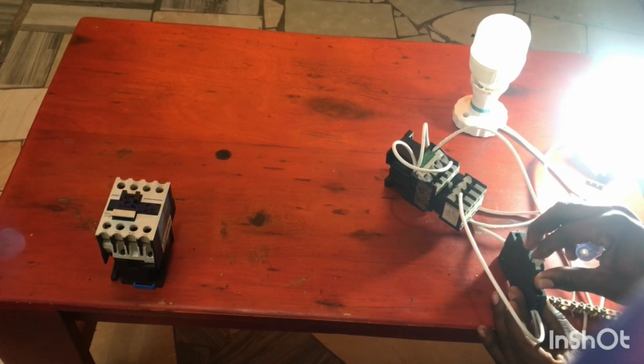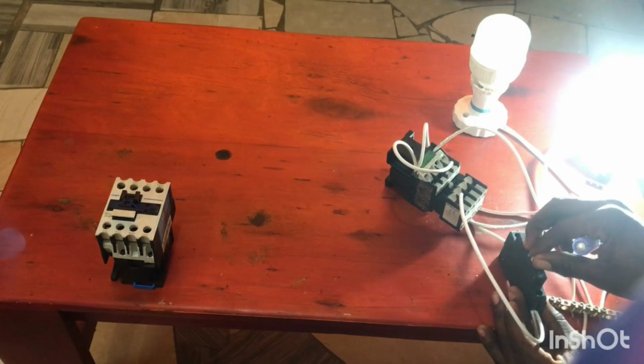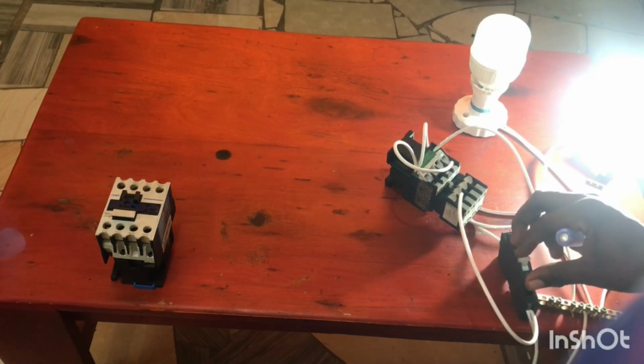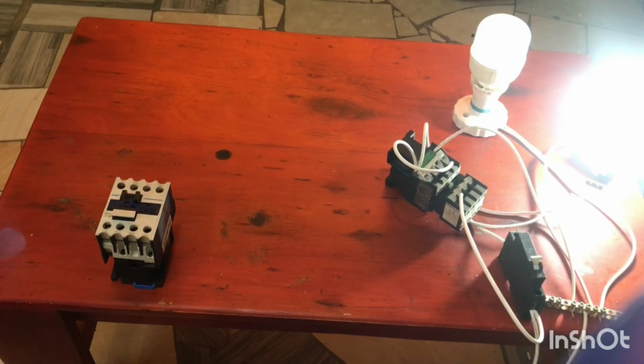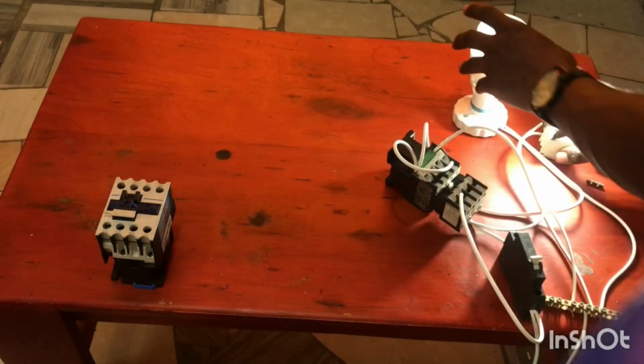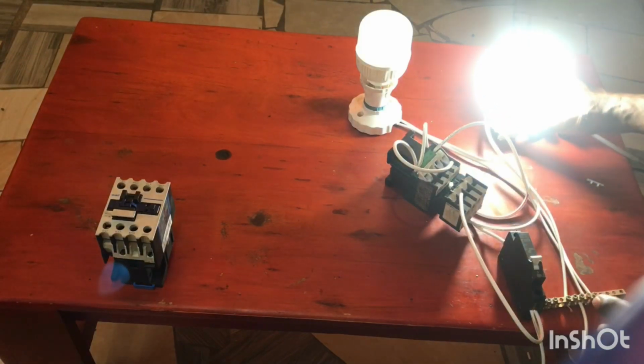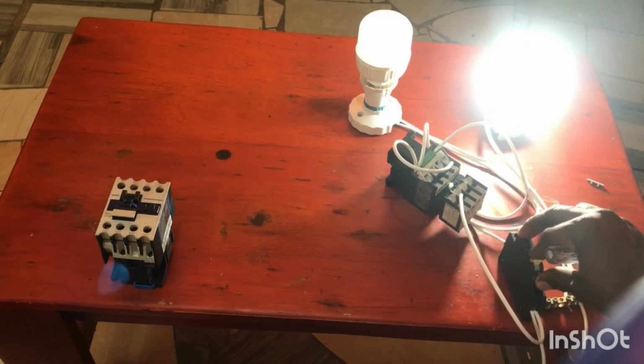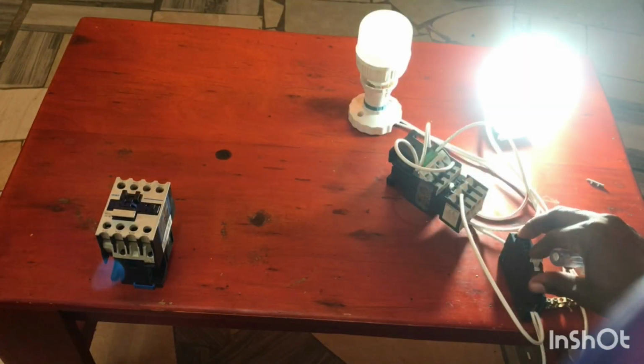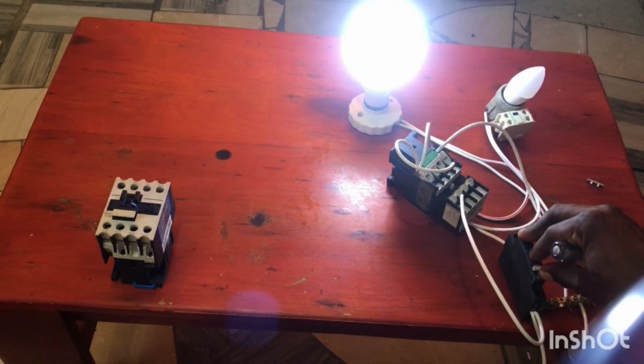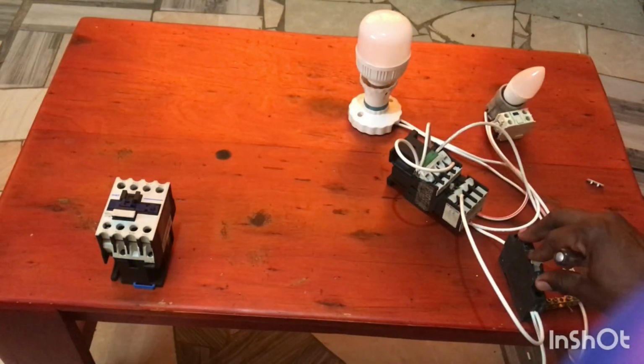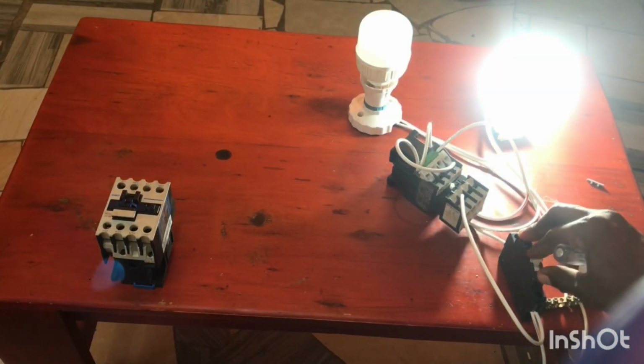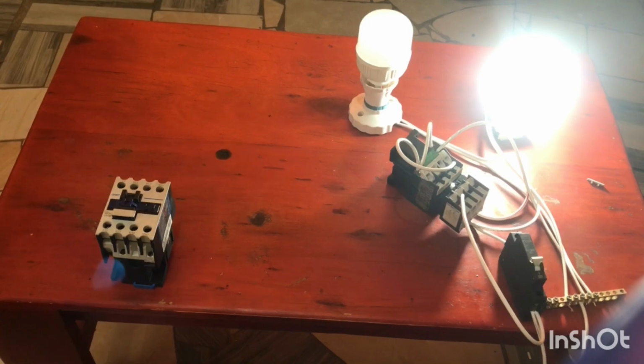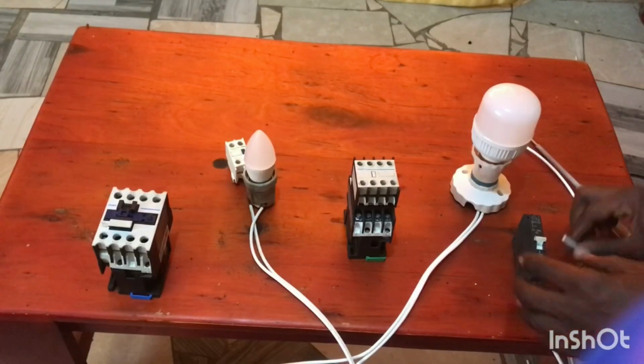So these two lights cannot work at the same time because one is at normally open, the other one is at normally closed. So this circuit works when you are making a generator changeover switch. When the genset is running, the main grid is not running. When the main grid is running, the genset is off. They don't work at the same time, they interchange. That's the principle of a contactor.